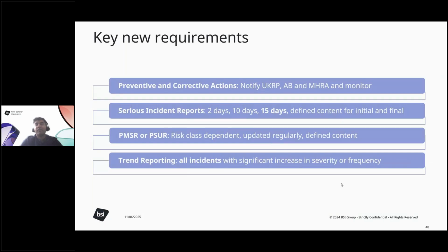So those are the key new requirements that I just wanted to set out. There are some specifics on preventative and corrective action, where you need to notify the UKRP, AB, and MHRA, and also monitor these. Serious incident report timelines are slightly different now. There are 2 days, 10 days, and 15 days, and these are defined for initials and finals in this PMS statutory instrument. There are requirements for PMSRs or PSURs, depending on the risk of the device, and these need to be updated regularly and defined, and may be reviewed by the approved body if there is one, but also the MHRA. Trend reporting is a requirement for all incidents with a significant increase in severity or frequency, so make sure you are starting to trend report as well.